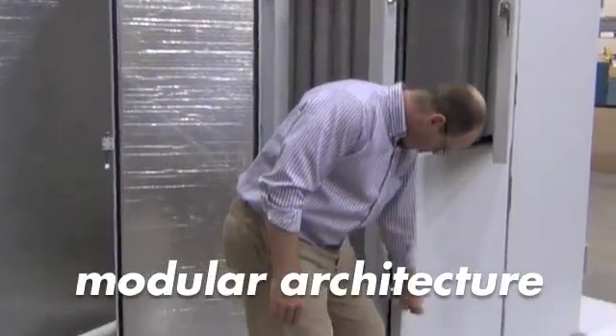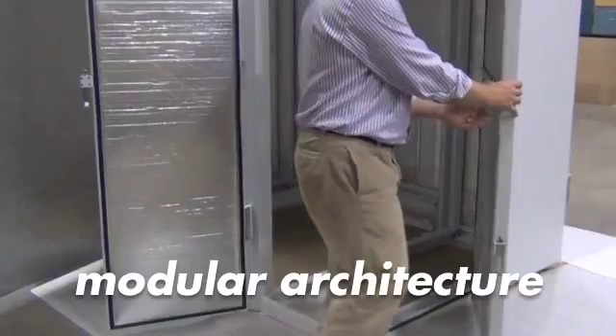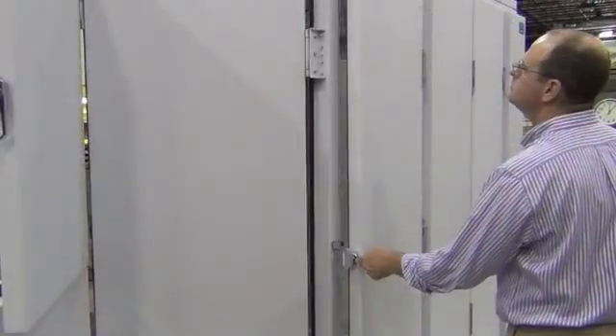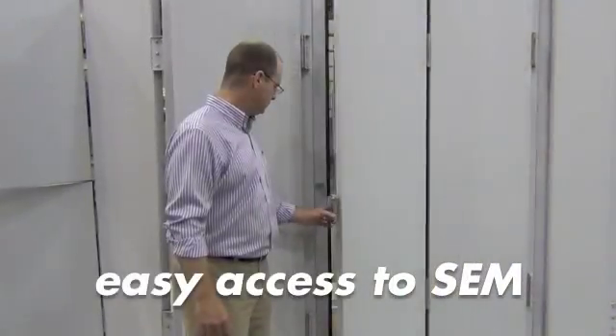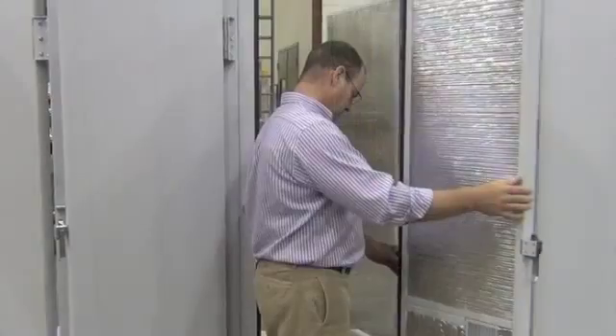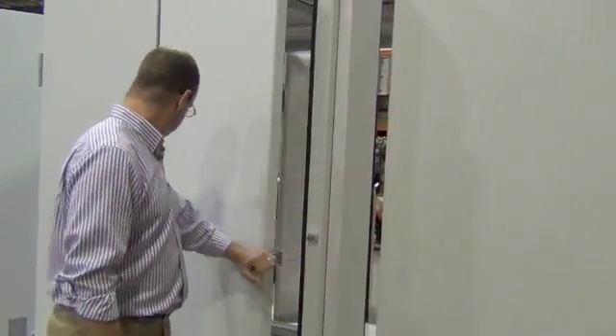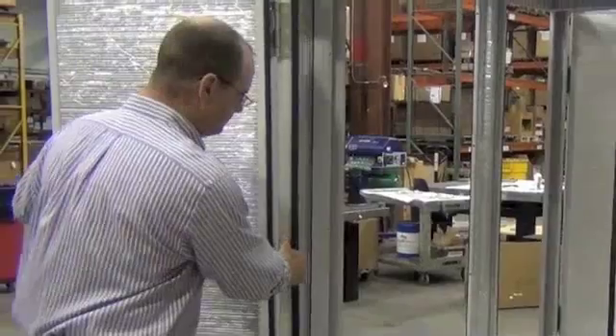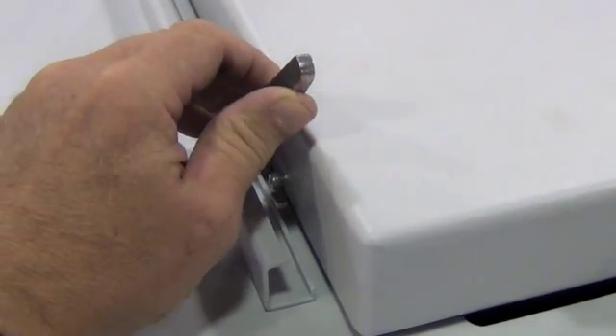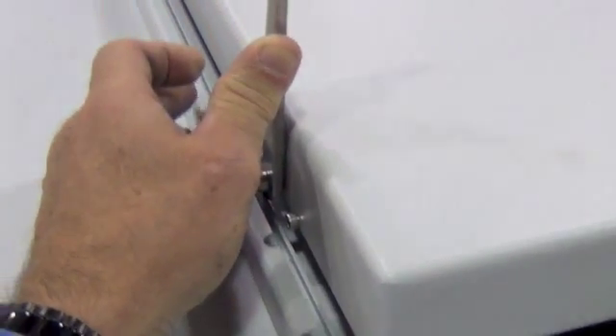The modular architecture allows ample space for virtually all commercial SEMs. Several hinged doors allow easy access to any side of the SEM for sample preparation, adjustment of accessories, and maintenance. Bi-fold doors on sides and rear help minimize clearance requirements. The top panel includes an easy open, space-saving hatch door for access to the top of the SEM.